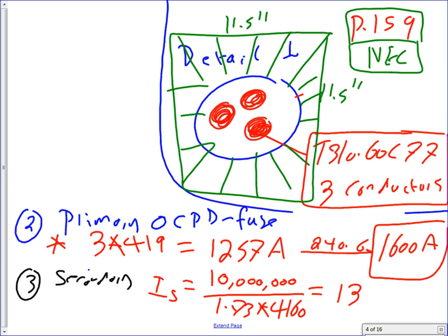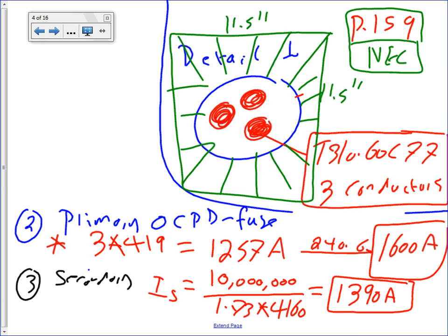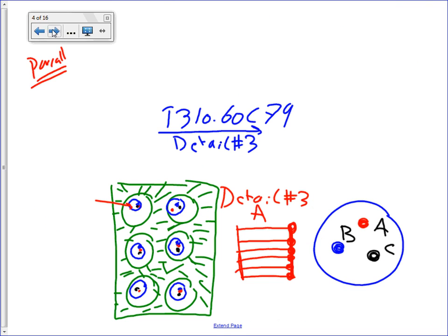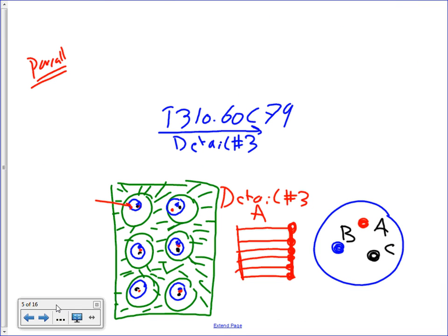4160. And if you guys do the math, what's my secondary? I have 1390 amp. 1,390 amps. Anybody came up with something different? 1389? 12.5. Close enough for government work. Okay. Does that make sense? Jeff? Makes sense? Okay. So I'm going to spend more time on the important stuff. Let's go down and do the calculation now.